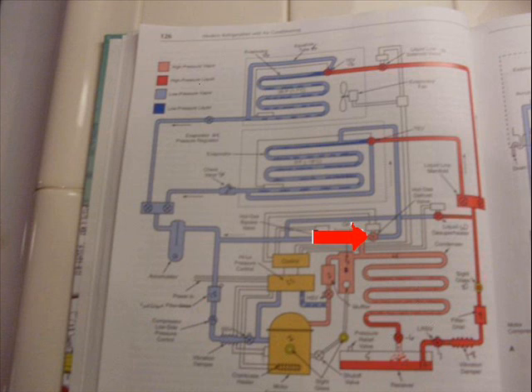So, when we go into defrost, we don't have this pressure gas coming back and slamming into our compressor, do we? And the accumulator is super important during defrost because some of this hot gas might be condensed into liquid droplets and the accumulator will catch those droplets. So, that's why you're going to have an accumulator on a hot gas defrost system, because you may have some of that gas turned into liquid droplets.